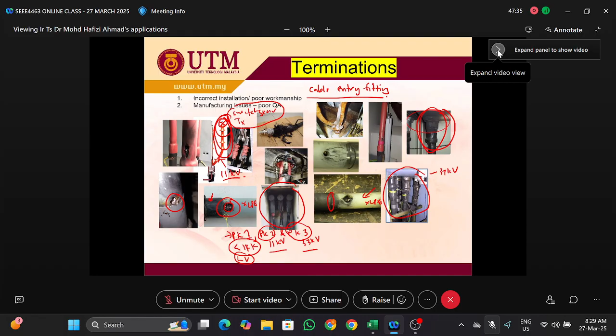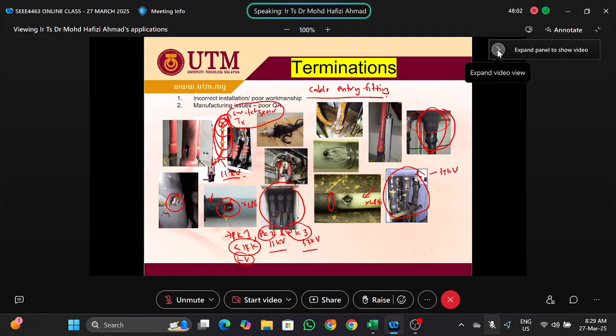So basically, this is XLPE, this is the insulation, and this is the semiconductor screen - what we call the insulator screen. This needs to be cut in a smooth line. If we have something like a non-smooth line or sharp tips, this can create non-uniform electric fields, and you might be able to see this as well in the cable joint.